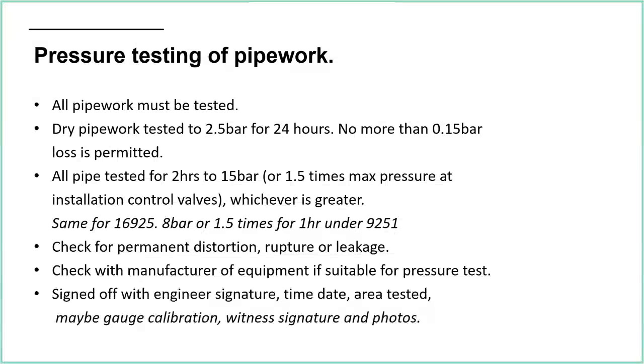But we just say in our instructions, it's best practice to isolate the pump. So there's valves either side of the pump. You close those, and then you do your hydrostatic test. So basically, the pump doesn't experience 15 bar, 18 bar, but the rest of the pipe work does. So that's an example of just being on the ball about the equipment that you've actually got installed on the pipe work. What do they say in terms of going up to high pressure?